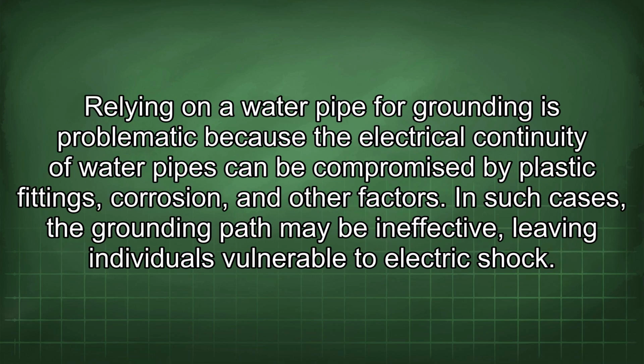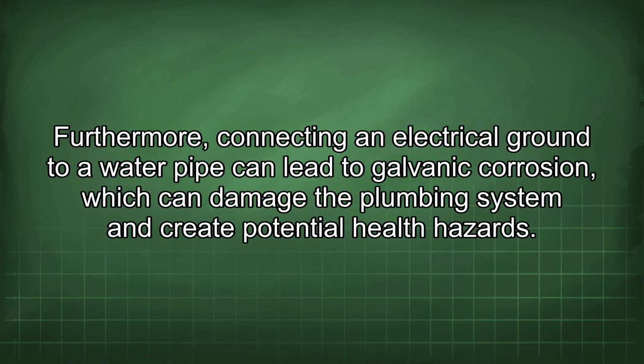Relying on a water pipe for grounding is problematic because the electrical continuity of water pipes can be compromised by plastic fittings, corrosion, and other factors. In such cases, the grounding path may be ineffective, leaving individuals vulnerable to electric shock. Furthermore, connecting an electrical ground to a water pipe can lead to galvanic corrosion, which can damage the plumbing system and create potential health hazards.